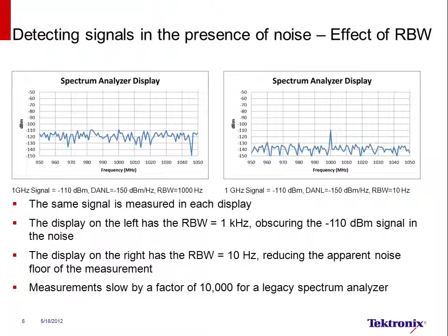The trade-off here is the instrument sweep time. The measurement example is being performed across a 100 MHz span. For a legacy swept spectrum analyzer, the sweep time would increase by 1 over the square of the RBW, or slow the sweep time by a factor of 10,000. This is a significant penalty in the measurement time, and many people would not wait for this measurement to be completed unless they really required such a low noise floor on the measurement. Note that with the real-time spectrum analyzer, there would not be this penalty because of the dedicated wideband architecture, and we will look more at this later in the presentation.